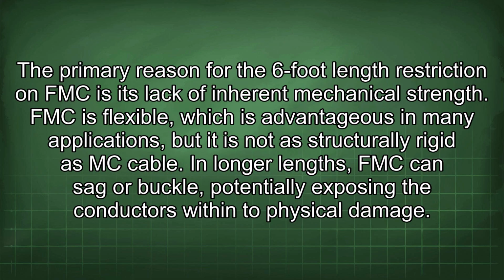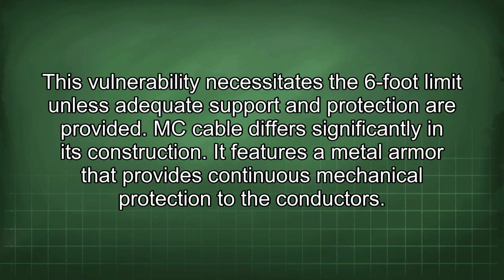The primary reason for the 6-foot length restriction on FMC is its lack of inherent mechanical strength. FMC is flexible, which is advantageous in many applications, but it is not as structurally rigid as MC cable. In longer lengths, FMC can sag or buckle, potentially exposing the conductors within to physical damage. This vulnerability necessitates the 6-foot limit unless adequate support and protection are provided.